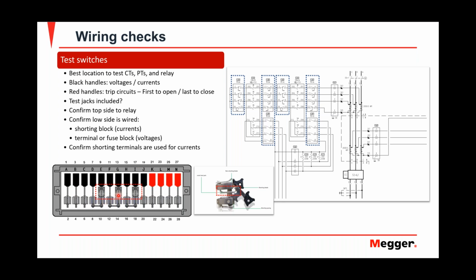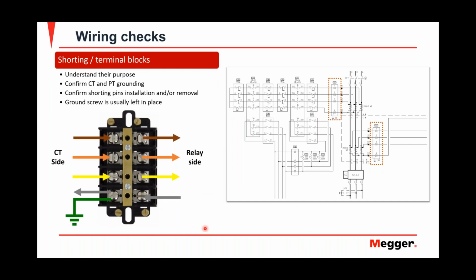Sometimes I also used to work, in my past life, with a switchgear manufacturer, and sometimes you got a new guy wiring switchgear and he doesn't know that these are for currents and the other ones are for voltage. And then you're the field engineer. These are things that you've got to catch and keep in mind. Don't assume that the guy who built it knew what he was doing. I'm going to pay special attention to the shorting blocks because it's safety wise one of the most important things when dealing with CTs.